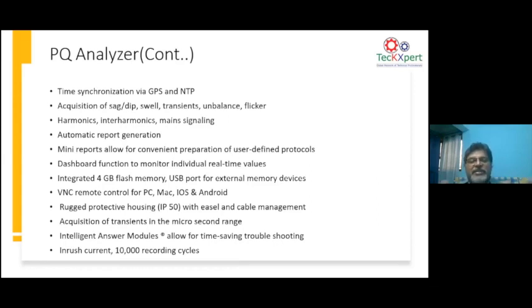So if you're doing a measurement, let's say in a factory, you can have multiple analyzers connected on a GPS network so that if an event happens, all the analyzers will timestamp it at the same time. That will give you a better analysis of the problem. Sometimes, when you do analysis, if a fault happens or there is an unwanted power quality event, the analyzer should capture the pre-fault, during-fault and post-fault waveforms. If the waveforms are captured correctly, then you can do something called waveform signature analysis. By doing waveform signature analysis, you can analyze exactly what the problem is.